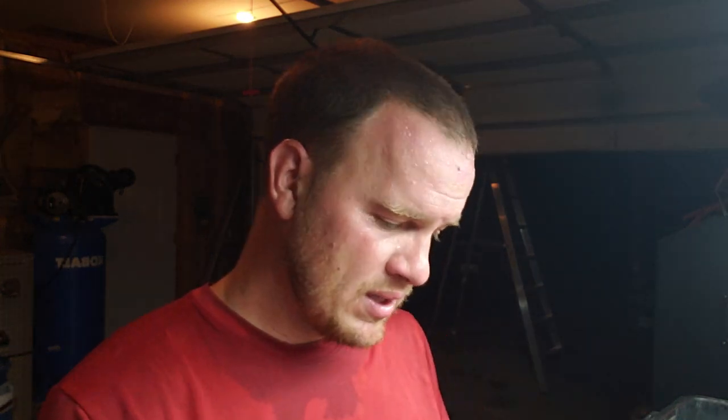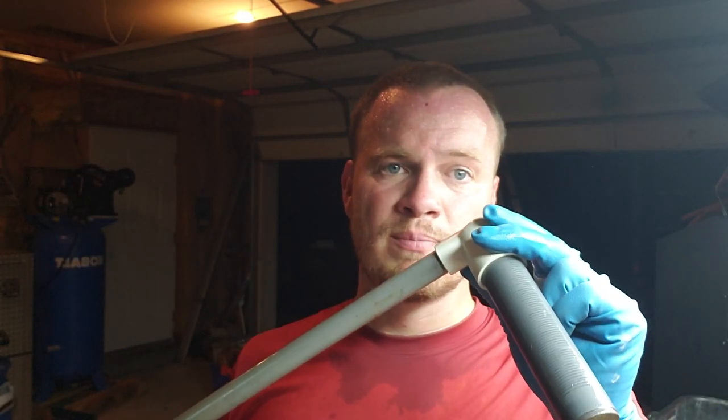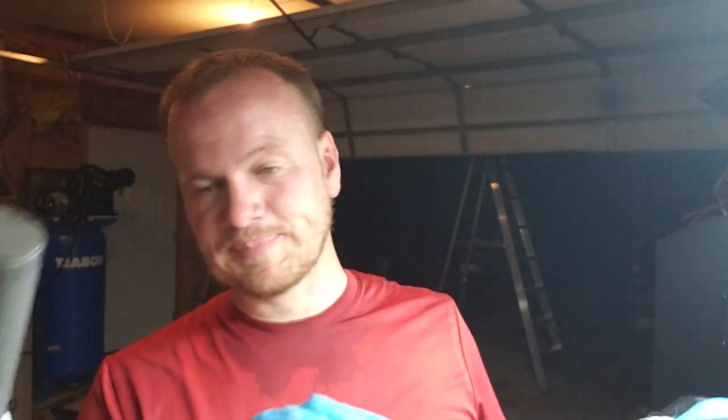The point of the Teflon is to let you get it in a little bit further and make it slide a little bit better. We've got our new ones here — we'll take the gasket off of it, hook it back in there, and be up and running tomorrow. If you're in the field, what we did the other day is literally took the thing out, had a half-inch ball valve — a PVC ball valve — threaded it onto here, threaded it onto that 90-degree fitting. We do the 90 to the ball valve first and then thread it to this because I can spin this sucker around all day long in the bottom of the tank. When you're putting these into your tanks, drill the hole so that it's more centrally located — don't try and put it in a corner. If it's 12 inches wide, put it 6 inches in and 6 inches away from the side. That way you can spin this thing around without breaking it and it just makes things a lot easier.